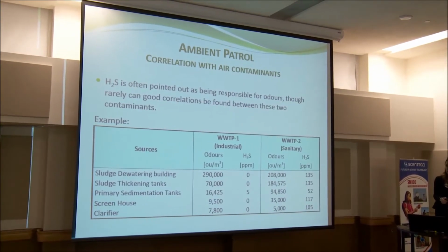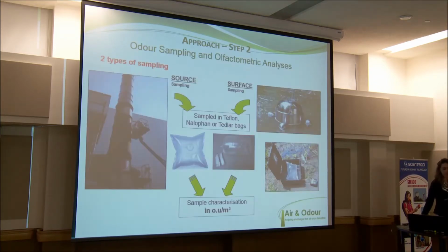Correlation with air contaminants. I was talking to you about hardly any correlation with H2S. You see two different wastewater treatment plants. One is industrial and the other is sanitary. And you see the odor levels pretty much match, but H2S doesn't at all.